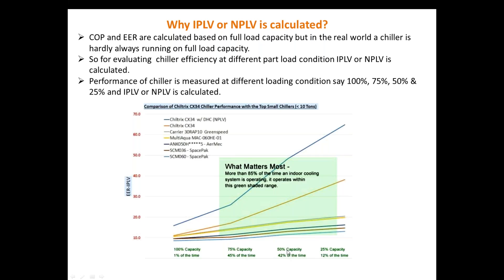The chiller works at 25 percent capacity about 12 percent of the time, and interestingly the chiller works at 100 percent of its full capacity only one percent of the time. This shows that the COP and EER values calculated are of no use because they are based on the assumption that the refrigerator or chiller works at full capacity — which only happens one percent of the time. Most of the time HVAC or refrigeration devices work on part load.